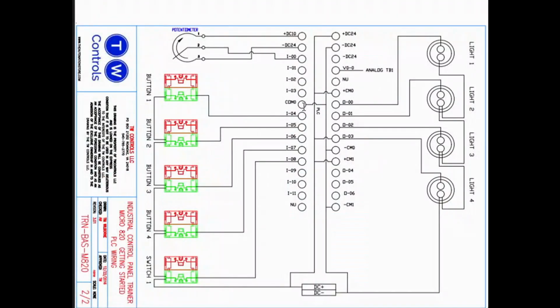So this is how you wire our Micro820 for the getting started exercises. And there is no difference between a light and a relay. We have plus 24 DC going to the plus CM0, and we have minus 24 DC going to the minus CM0. And so each one of these is now sourcing voltage out, or sending positive voltage out to the light.